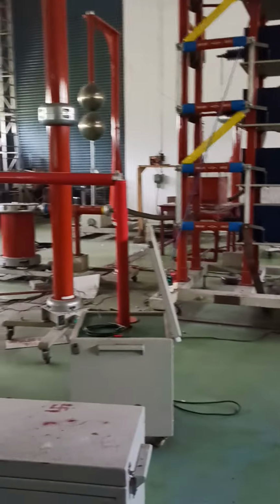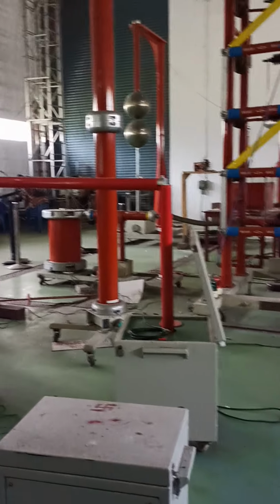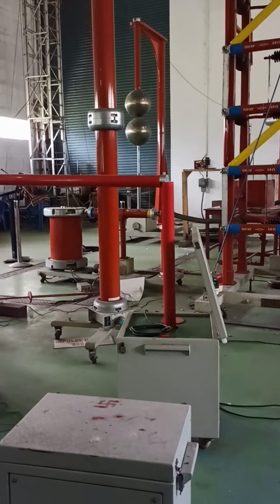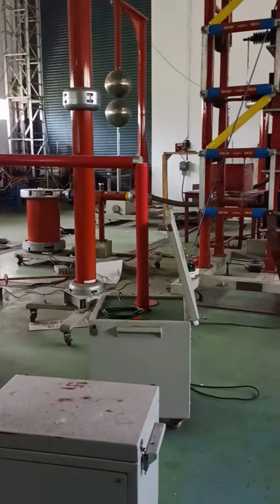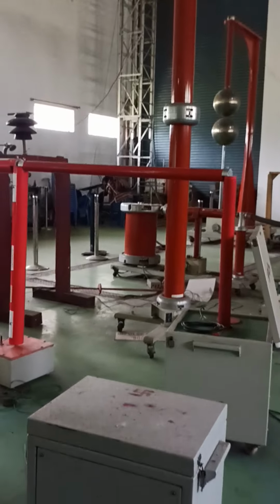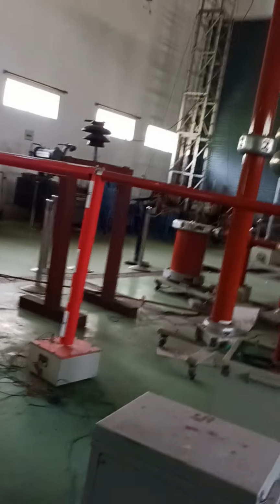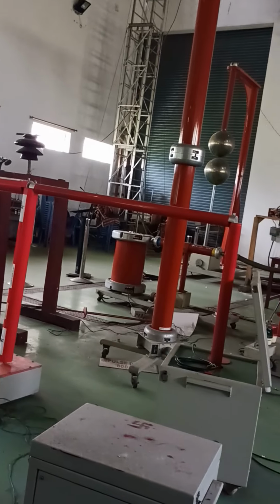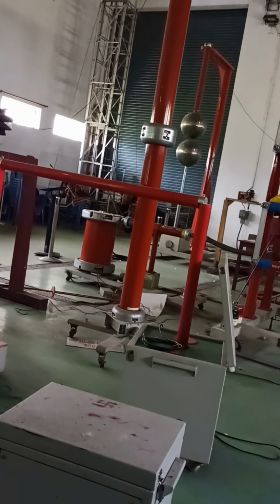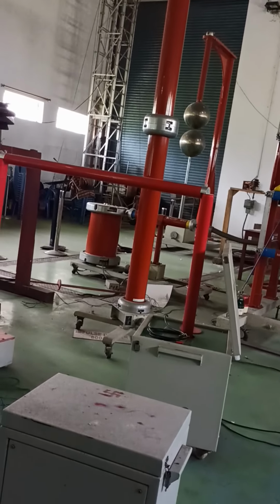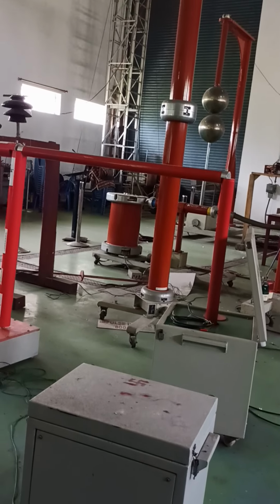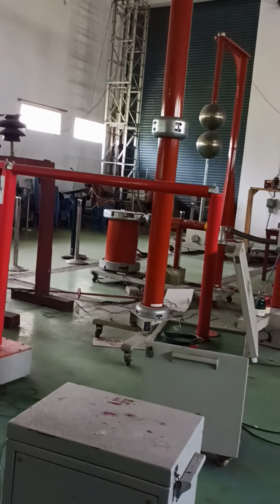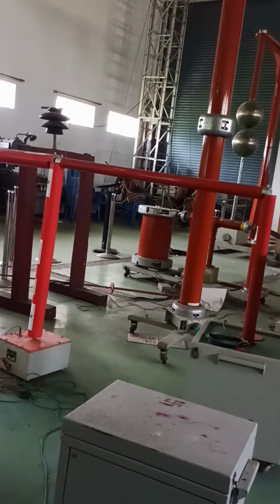Right, it's not about charging. What happens is that every oil has impurities. We cannot directly use that oil inside and just start it. The oil may contain some pollutants that may directly short circuit the transformer. So first we need to heat the oil, and we need to filter the oil.